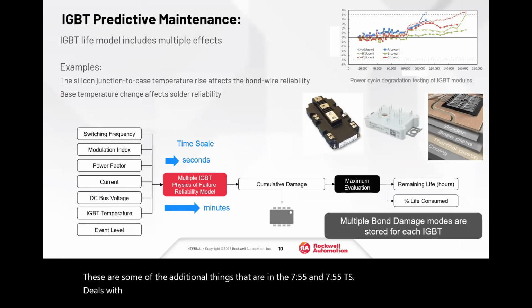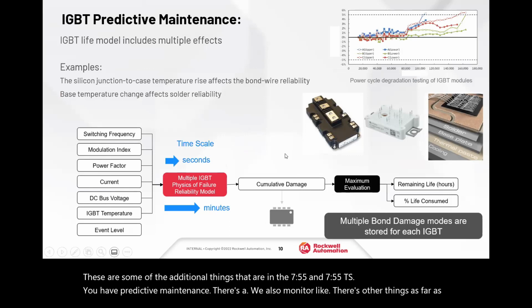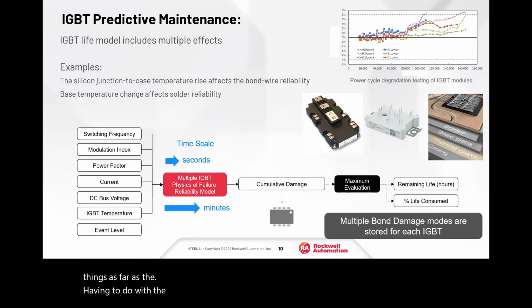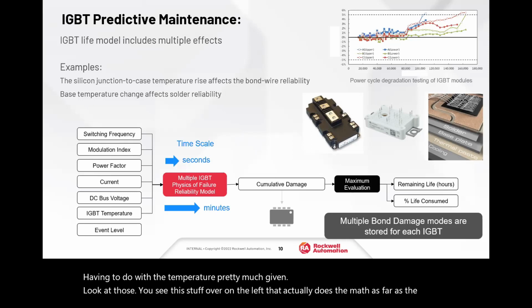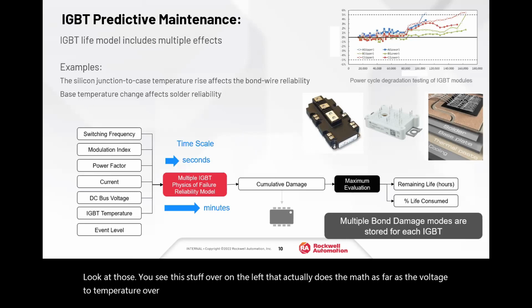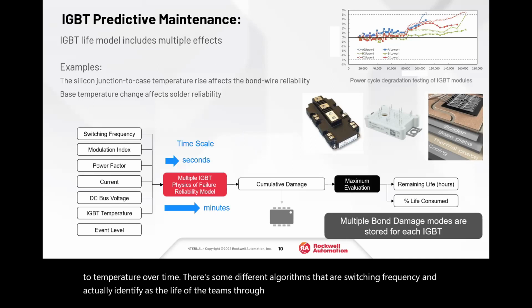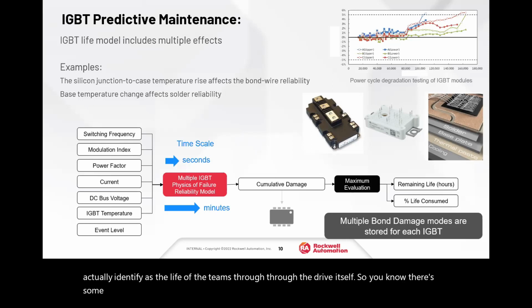You have predictive maintenance. We also monitor things like the fan life, and there are other things having to do with the IGBT temperature. Those are pretty much a given. But if you look at this, you can see the stuff on the left that does the math for IGBT voltage and IGBT temperature over time. There are different algorithms in here, including the switching frequency, and it identifies the life of the IGBTs through the drive itself. So there are things you can do with predictive maintenance to stay ahead of any failures if you have a critical application.